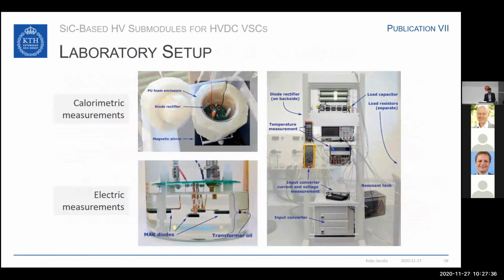For both, we have put the diodes into transformer oil. This transformer oil served as a cooling medium, but also insulation medium. For the calorimetric measurements, we have placed the diode rectifier into a foam enclosure, and then measured the temperature increase. For the electric measurements, we measured the current and voltage at one diode.